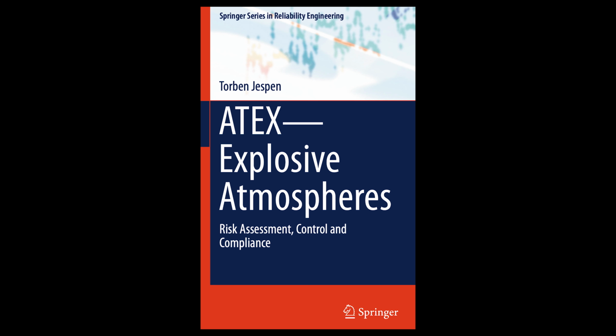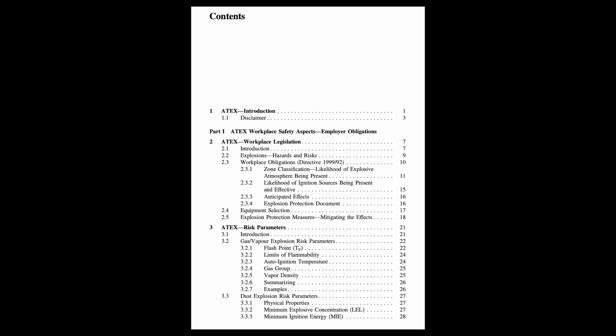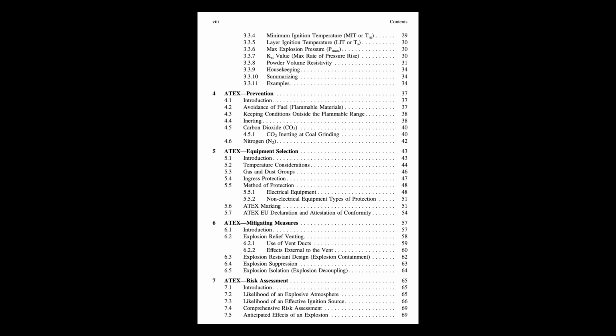Okay. How does the idea of grade of release fit into zoning? The grade of release describes the source itself, how likely it is to leak or release the flammable substance. There are 3 grades: continuous release, like vapor space in a tank; primary release, expected during normal operation, like sampling; and secondary release, not expected normally, only occurs under fault conditions, like a flange leak. And these grades link directly to the zones.